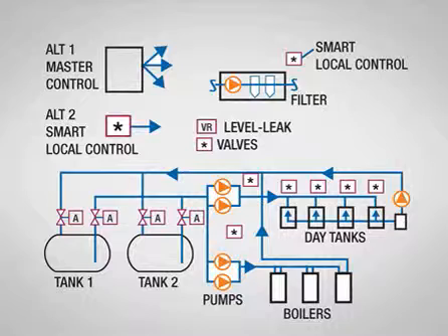The fuel system will consist of equipment elements that perform a specific function and interact with other system elements. The primary elements are: 1. Generator day tanks, 2. Fuel transfer pumps, 3. Tank storage and tank selection, 4. Tank fill systems, and 5. Tank filtration monitoring. The control system options are distributed or master.